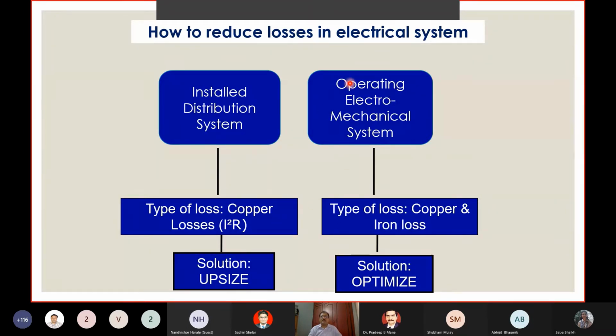So far as the operating electromechanical system is concerned, the losses include copper and iron losses. Now, one rule of thumb that everyone will tell you is that when the two losses are equal, the best efficiency occurs. This is true for motors and also for transformers. For most electromagnetic instruments and equipment, when the copper and iron losses become equal, the best efficiency happens. Therefore, the solution for the operating electromechanical system is to optimize. So we have upsize and optimize. We should classify our solutions under these two.